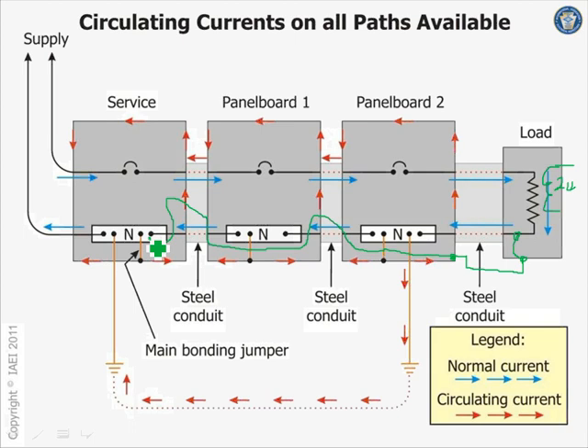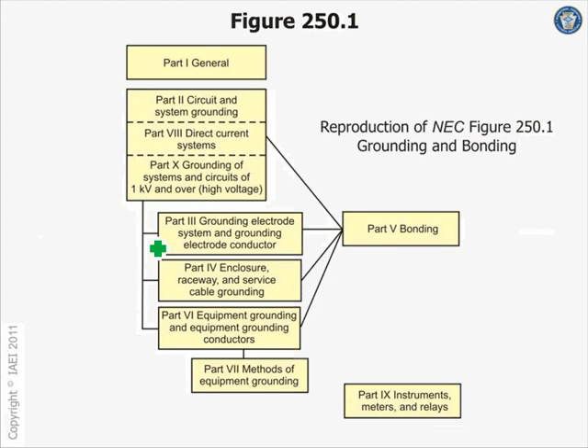At the equipment level. Now, what your issue is, if you have a ground fault detection here, you will trip the equipment. If you have a ground fault protection in this system and you do it this way and you're tying it, because the ground fault is looking at the current coming back at the ground, you could trip the ground fault because of that current.